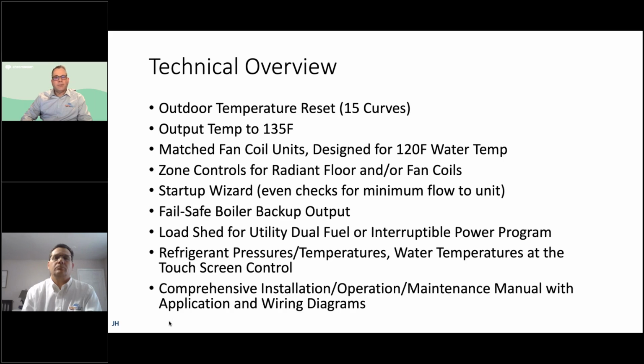I sat through a California Energy Council webinar yesterday, and there's a lot of discussion on leveling the peaks, doing load shed, managing the demand, but also managing the renewable electricity generation. So this is prime for those types of applications or retrofits where maybe they don't have 200 amp service in the home. All of the pressures, temperatures, water temperatures are shown at the control screen. So from a troubleshooting standpoint, you don't have to hook up any gauges. You don't need your thermometers. You can read those right at the screen.